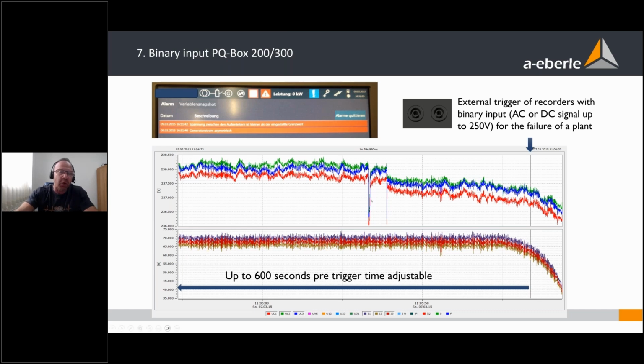And here was a nice story. A big machine permanently stopped running, and the reason was a really small voltage dip. And we see a voltage dip of only about 2 volt. And no analyzer normally triggers on a voltage change of 2 volt. But we trigger here on a binary output of the machine. We see here the problem. The machine goes down. You see it on the current. And we look back. And here we can prove that the network is not responsible or the reason for tripping this machine.